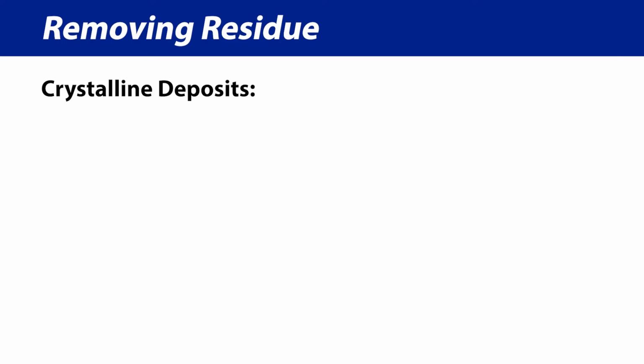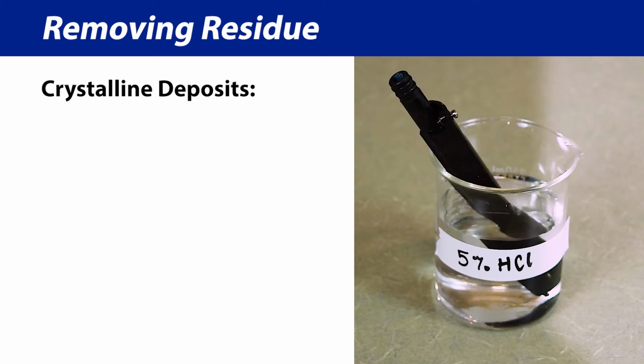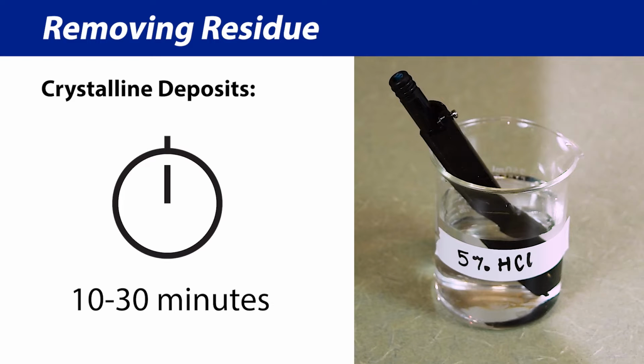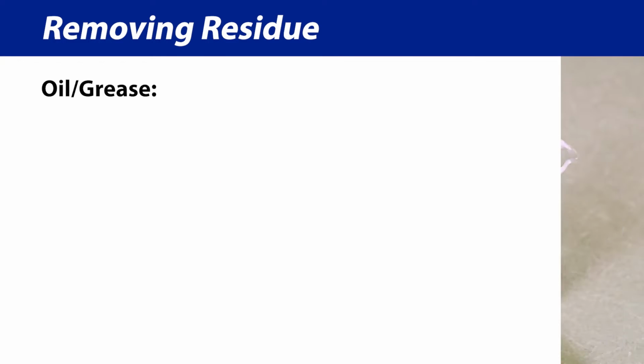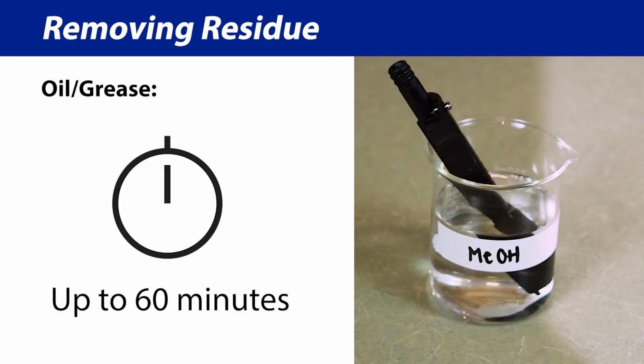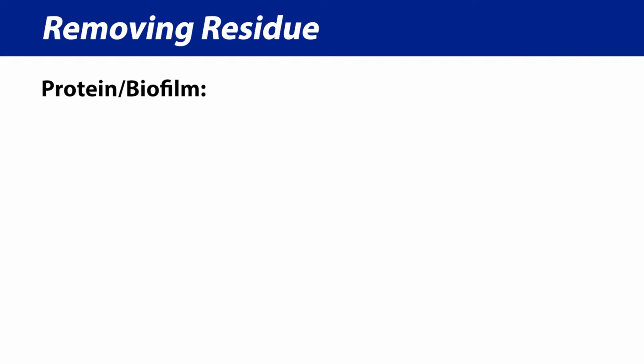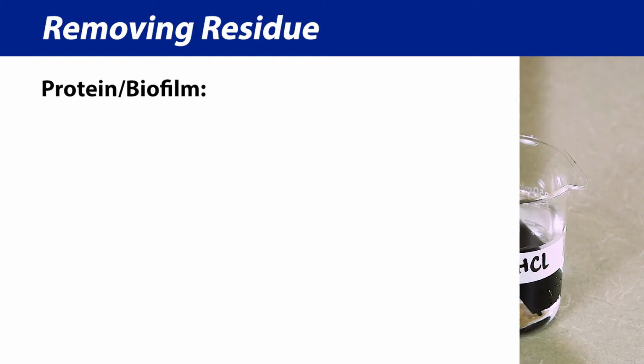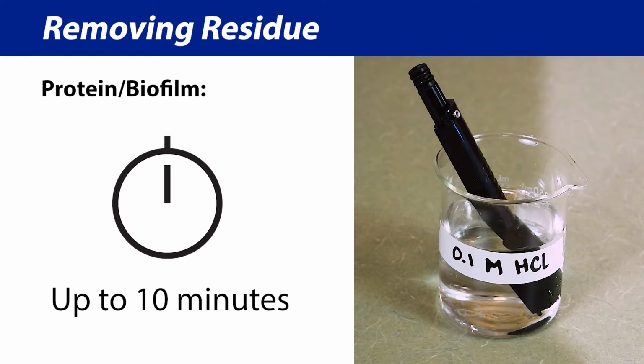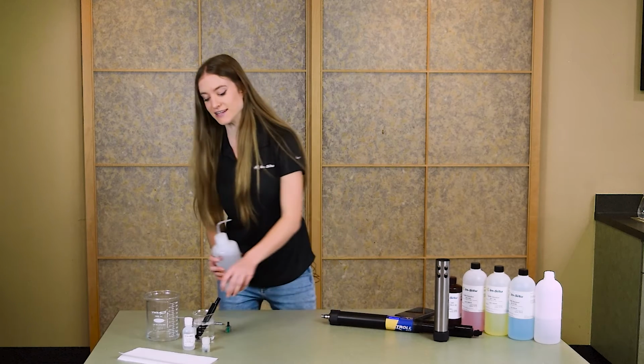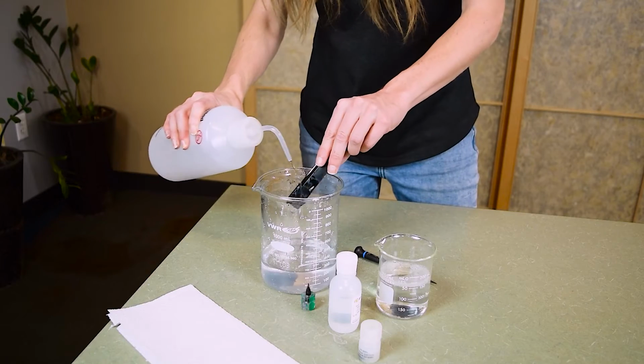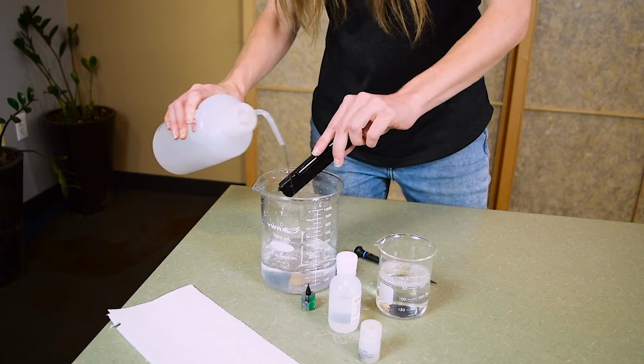For crystalline deposits, soak the sensor in 5% hydrochloric acid for 10 to 30 minutes. For oil and grease, soak the sensor in methanol or isopropyl alcohol for up to an hour. For protein or biofilm, soak the sensor in 0.1 molar hydrochloric acid for up to 10 minutes. Whatever cleaning solution you've used, make sure that you rinse the sensor thoroughly with water after cleaning.